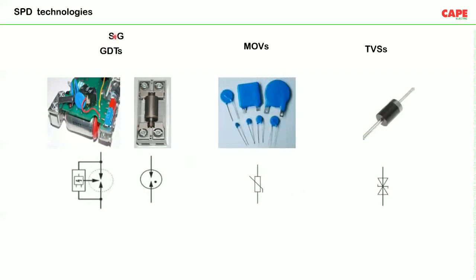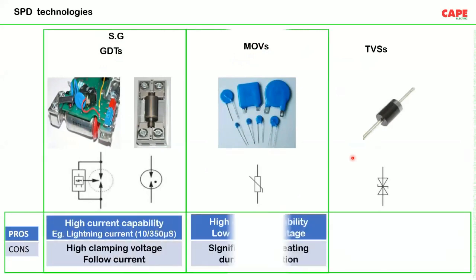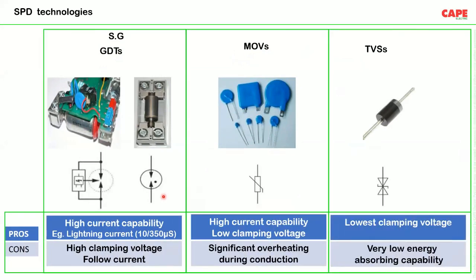Conventionally, the devices are classified into spark gaps or GD tubes, which are voltage switching type devices, metal oxide varistor, and TVSS. If you look at a small comparison between these three devices, the advantage of spark gap is high energy handling capacity. It can handle 10/350 microseconds, and its problem is high voltage clamping and follow current. MOV has high current capability, low clamping voltage, but significant overheating during conduction. And the TVS, like the silicon avalanche diodes, has the lowest clamping voltage and very low energy absorbing capacity.